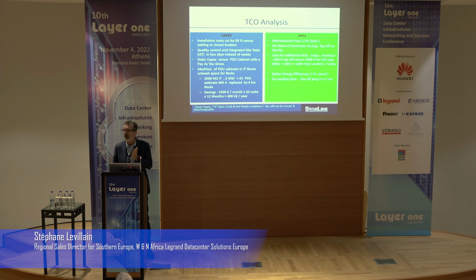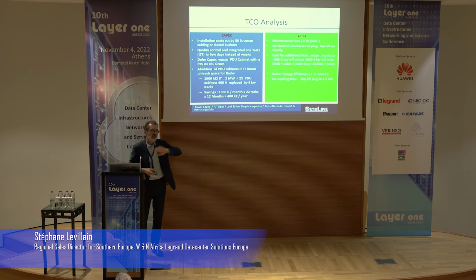Installation costs are cut by 50%, quite a lot. That's due to most tests being done in the factory instead of on site, so the integrated site test (IST) can be done in a few days instead of weeks or months, because testing every cable from the PDU cabinet to the rack is not easy. In terms of CapEx, you have to install all the busway if you want to start new business racks, but you can buy the tap-off step by step.